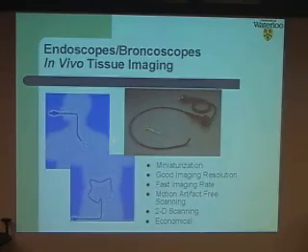One thing that I would like to mention is that currently, if we want to perform OCT imaging within the colon, it's usually a line scan, which means that the mirror would rotate in 360-degree format. We would actually direct the light beam at 360 degrees to perform a line scan. The problem with that is usually physicians are only interested in a small portion of tissue. So 90% of the time we are directing photons to the wrong places. The other thing is we want to achieve a 2D scan. We want to achieve an area scan rather than a line scan.